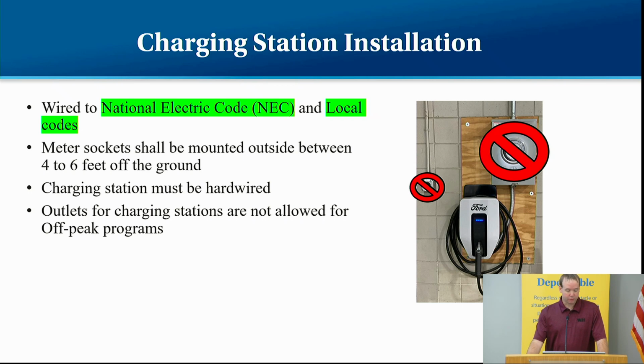The charging station must be hardwired, and outlets for the charging stations are not allowed. There's a couple of reasons for that. One is we need to make sure that we are metering their charger. The other is we don't want them to plug in and get the good rate overnight, but then plug in during our peak and start charging during our peak, causing problems with demand. They could do that by charging into a welder outlet just a few feet down. So that's one of the reasons why it needs to be hardwired, so that if they charge during the peak, they're going to pay the rate for charging during the peak, and it keeps them on the program, and we know that we're metering their car.